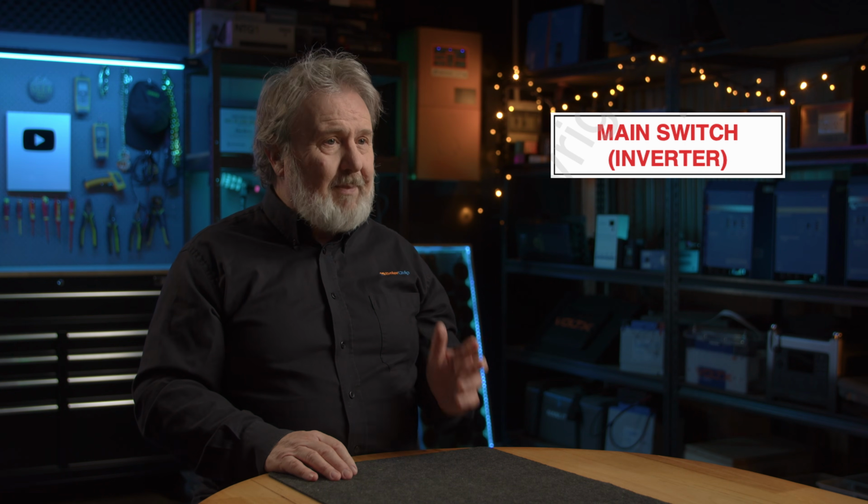Number 2, main switch, brackets, inverter. Yep, this is the label for the supplementary supply. But what's weird is the standard avoids using the word supplementary on the switch label itself. So it's just the good old main switch, brackets, inverter. Now, supplementary supplies are those that parallel with the grid, such as a standard grid tie inverter. A solar grid tie inverter is a supplementary supply.